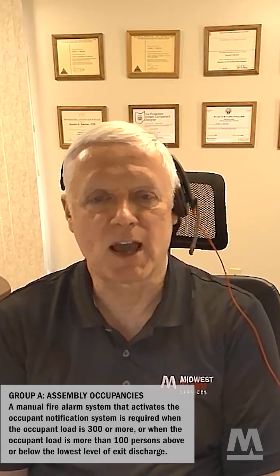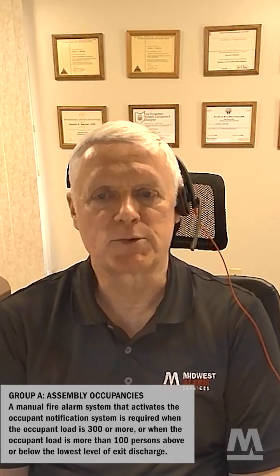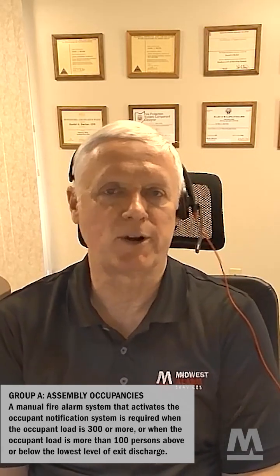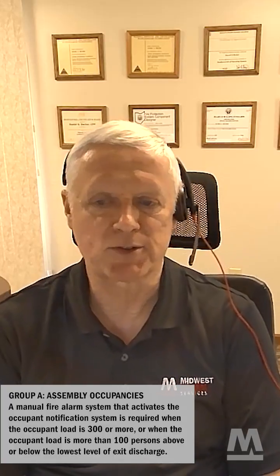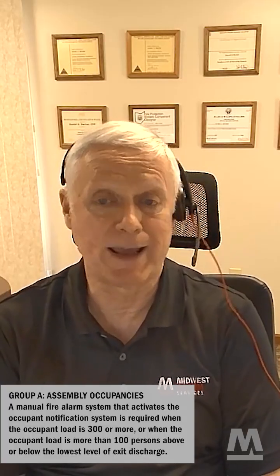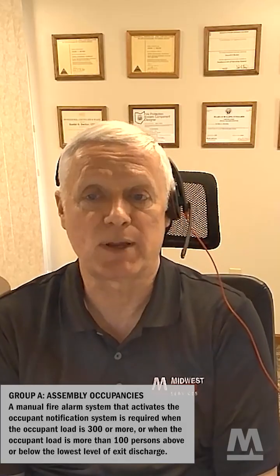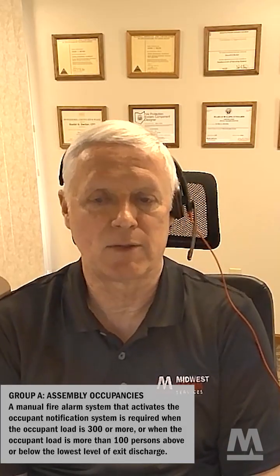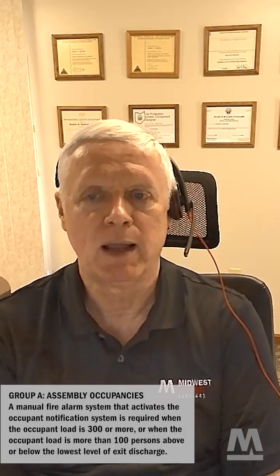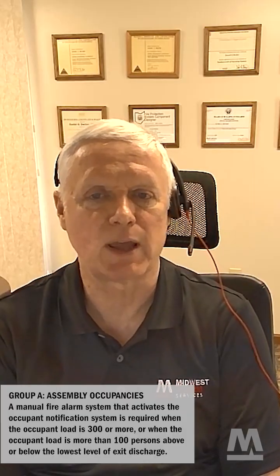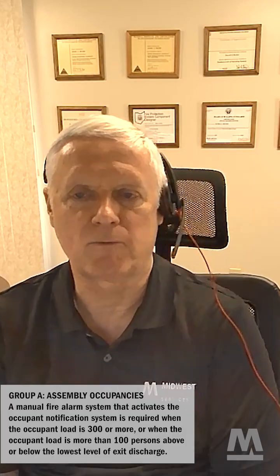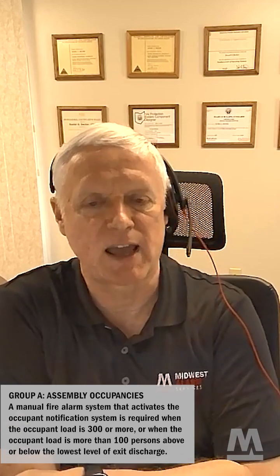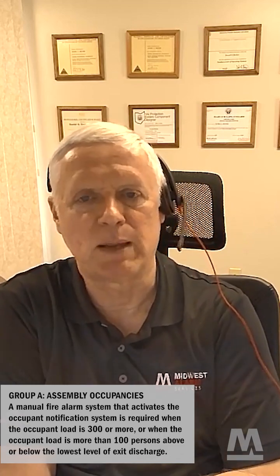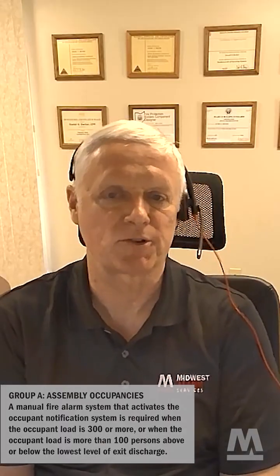Depends. A manual fire alarm system that activates the occupant notification system is required when the occupant load is 300 or more. If you've got a restaurant that will be an A occupancy and it has less than 300 occupants, then no fire alarm system is required. If it's 300 or more, then yes, we have to have a fire alarm system. And there's another caveat that if we've got more than 100 people, either above or below the level of exit discharge, that also triggers it.